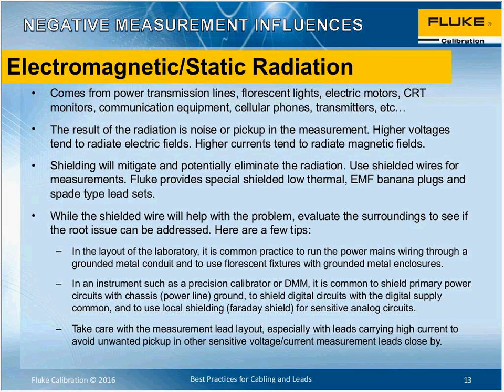If you've got interference coming into your circuits and make a measurement like that, the chances are you'll get a result that's wrong, and the result will be higher than you expect, because the unwanted signal is adding into your measurement. This is particularly so if your DMM has a 1 megahertz bandwidth and you're getting some pickup from a high frequency fluorescent fitting, for example, where you might have frequencies in the tens, twenties or hundreds of kilohertz. That would be within your measurement bandwidth. They'll add in and make your answer wrong, typically higher.